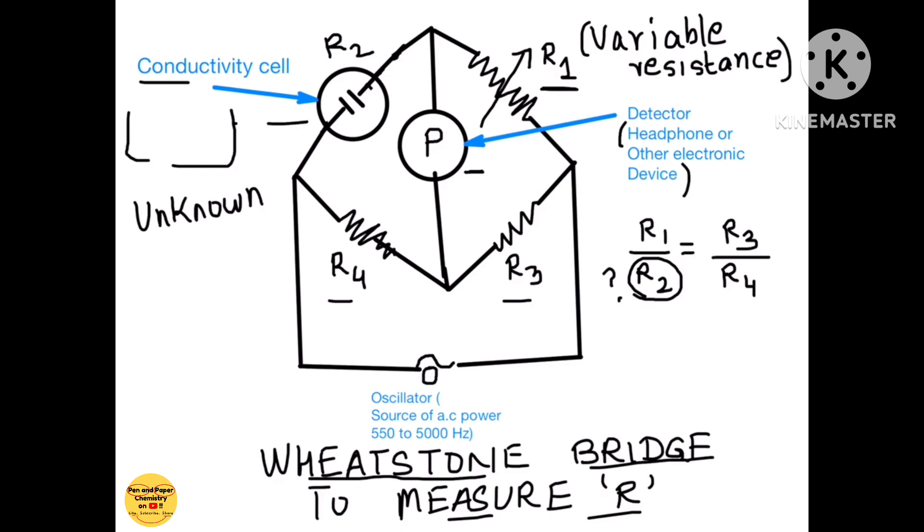If we pass current through this solution, through the electrolyte, we have also read about electrolysis. Electrolysis may take place and this may bring about a chemical change in the electrolyte. So our very purpose is lost. To counter that problem we are using an oscillator over here which is nothing but a source of AC power in the audible range of 550 to 5000 hertz. So that removes the defect or the drawback of the solution getting electrolyzed.